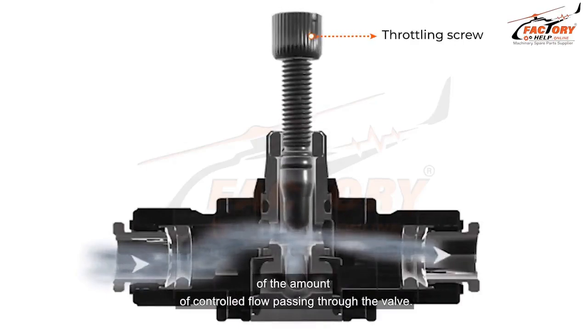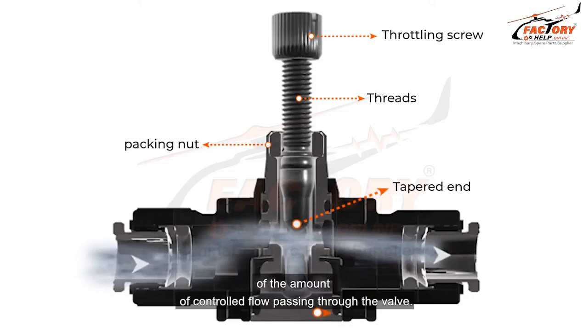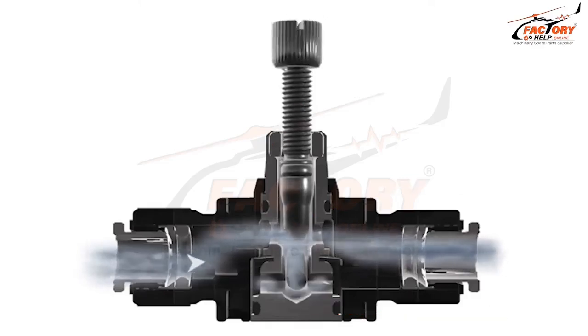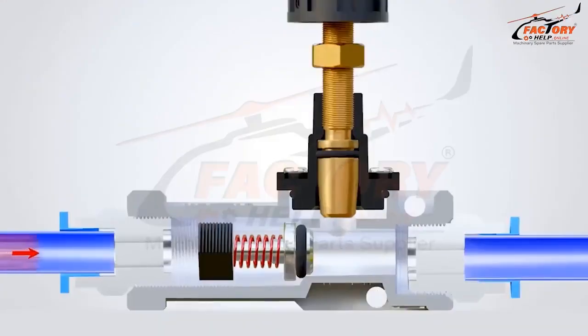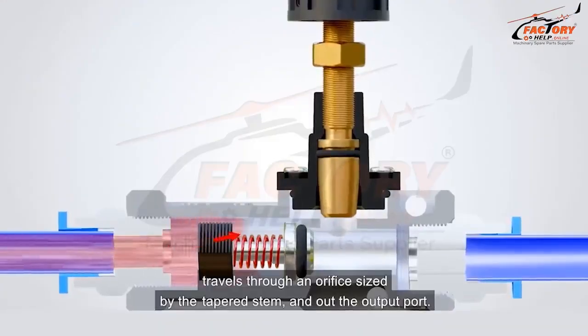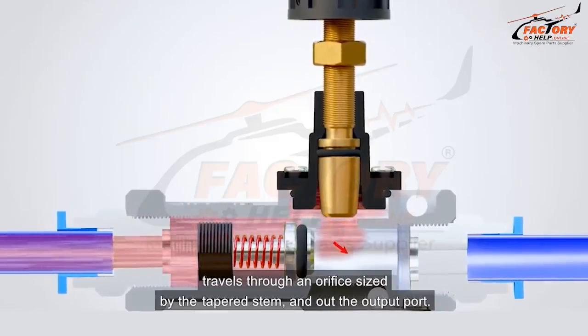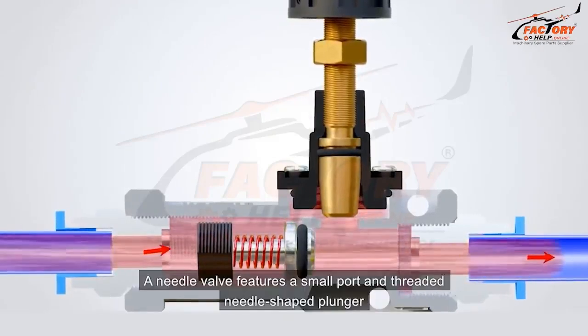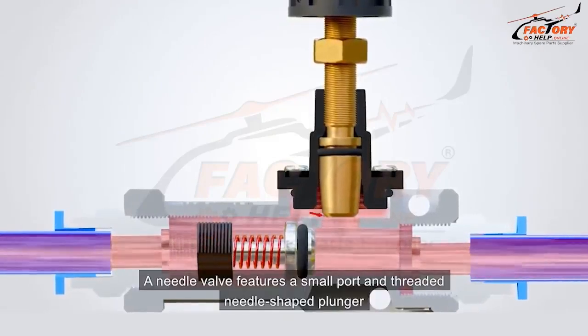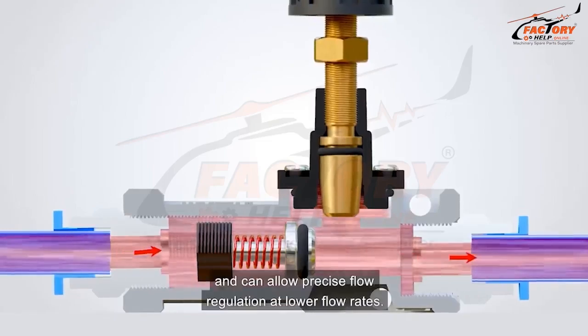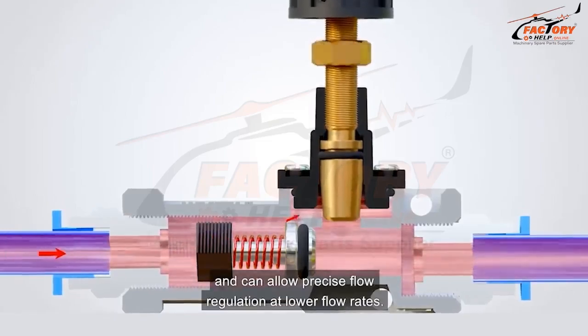Throttling screw, threads, tapered end, packing nut, valve housing. Flow enters the input port, travels through an orifice sized by the tapered stem, and out the output port. A needle valve features a small port and threaded needle-shaped plunger, and can allow precise flow regulation at lower flow rates.